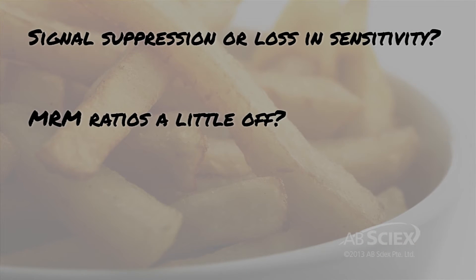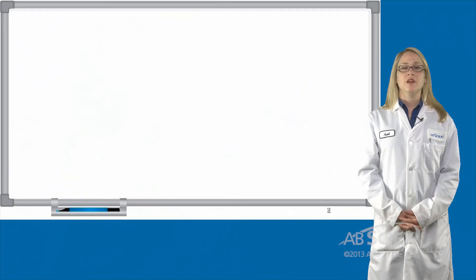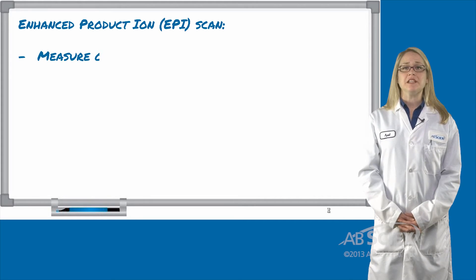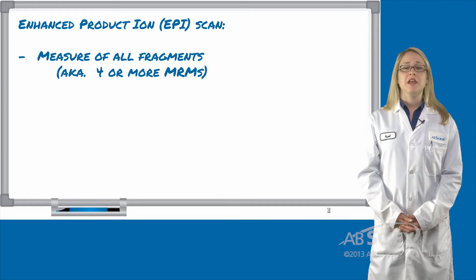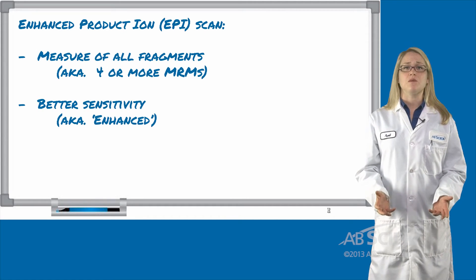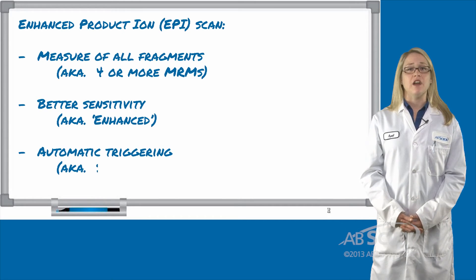Have you ever looked at your MRM ratios and thought that they are just a little off, and you're just not sure if this is a contaminant or a matrix effect? Q-TRAP can help you answer these questions. When using Enhanced Product Ion Scanning, or EPI, with Q-TRAP, it is basically like collecting more than four MRMs for any detected compounds in your sample. This means that if your MRM ratio is slightly off, or you get suppression that reduces sensitivity of your signal, you are able to get a sensitive measure of other fragments. Think of it as collecting data on more than four MRMs without any additional effort — it's automatic.